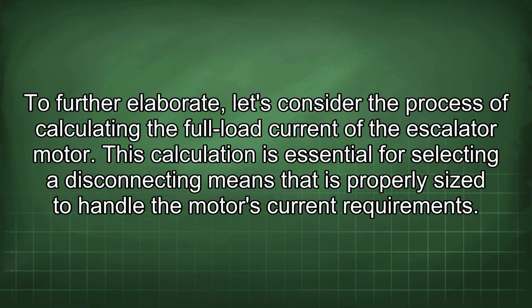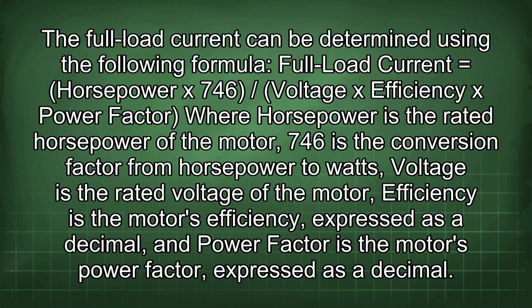To further elaborate, let's consider the process of calculating the full load current of the escalator motor. This calculation is essential for selecting a disconnecting means that is properly sized to handle the motor's current requirements. The full load current can be determined using the following formula. Full load current equals horsepower x 746 / (voltage x efficiency x power factor), where horsepower is the rated horsepower of the motor, 746 is the conversion factor from horsepower to watts, voltage is the rated voltage of the motor, efficiency is the motor's efficiency expressed as a decimal, and power factor is the motor's power factor expressed as a decimal.